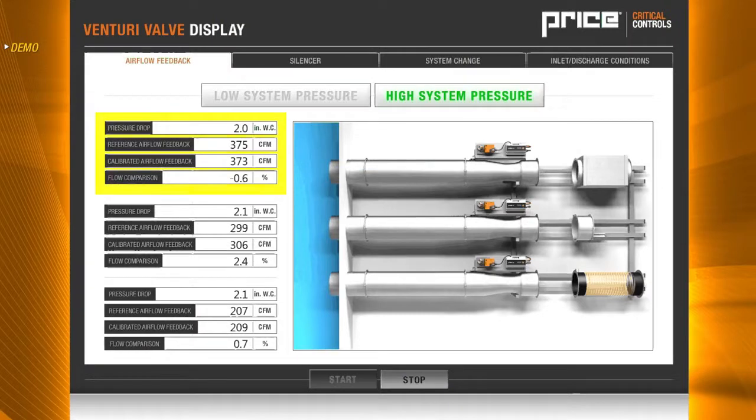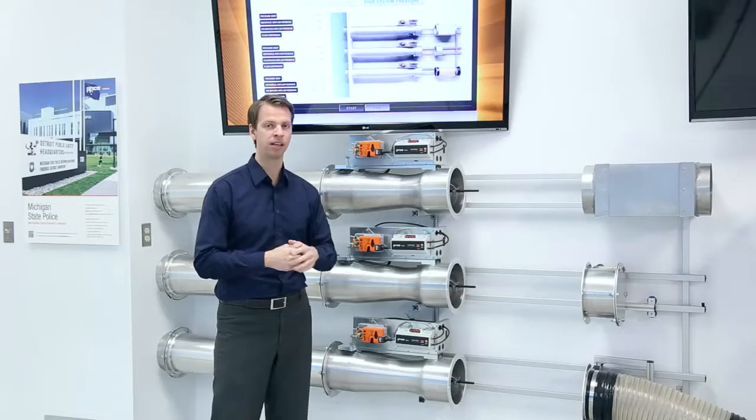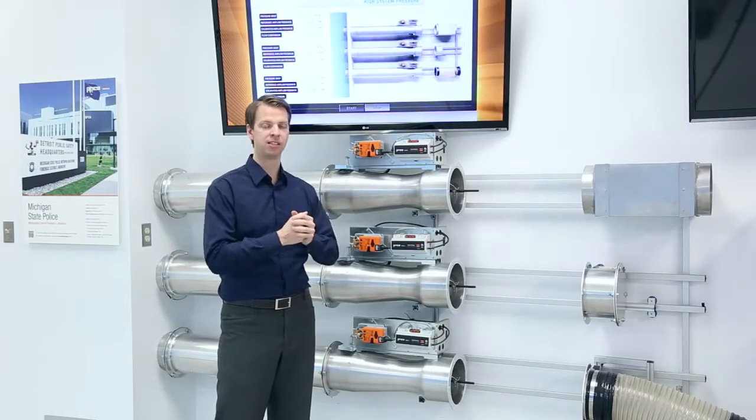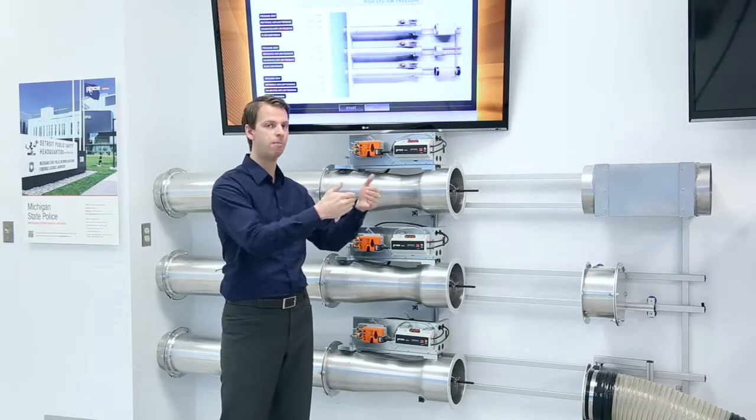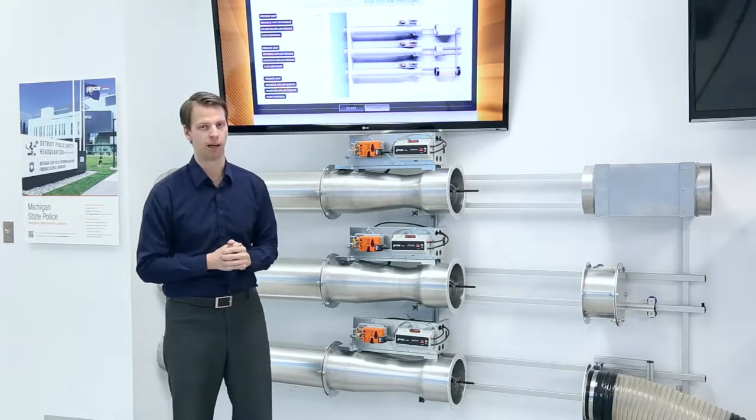While maintaining our airflow, our actuators maintain in place. We are in a constant position but the internal cone assembly senses or sees the increase in duct static pressure and makes that change to maintain our airflow set point.